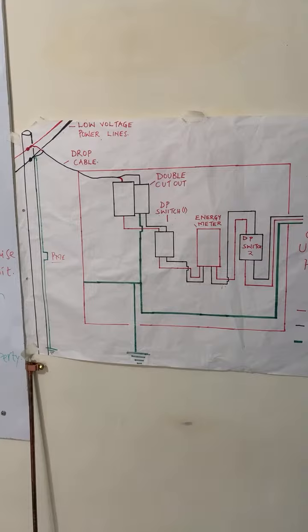And this is where you must be very intentional when you are purchasing these items, because when you purchase a brand that does not really understand that particular connection, you will find that you have done your electrical installation, but the customer is complaining, or the meters are giving an error of a bypass, for instance, if we may use that example.